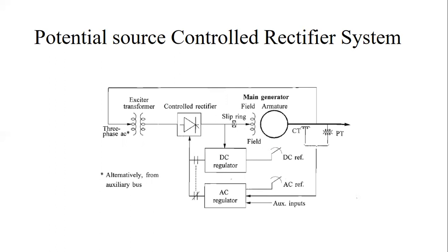This limitation of the excitation system is to a large extent offset by its virtually instantaneous response and high post-fault field forcing capability. In addition, it is inexpensive and easily maintainable. For generators connected to a large power system, such excitation systems perform very satisfactorily. Compounding ancillaries such as those described are not normally justified. They are likely important for generators feeding power directly into small industrial networks with slow fault clearing.